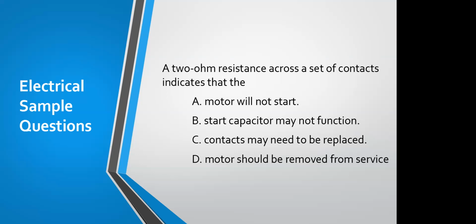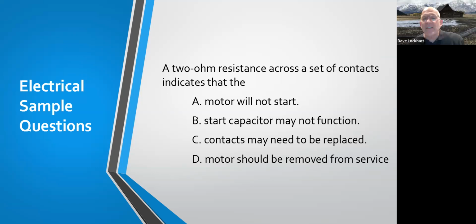Phil Harrigan put C in the chat box. Excellent. I can't see the chat, so thank you for that, Phil. Exactly. Contacts may need to be replaced. Yes, your motor may not start, but across the contacts we don't want any resistance, especially 2 ohms. That's going to create heat. As I mentioned before with Ohm's law, our contacts should be clean and make good contact. So having 2 ohms resistance across that contact would probably say it needs to be replaced. Great answer, Phil, and hopefully that makes sense for folks.